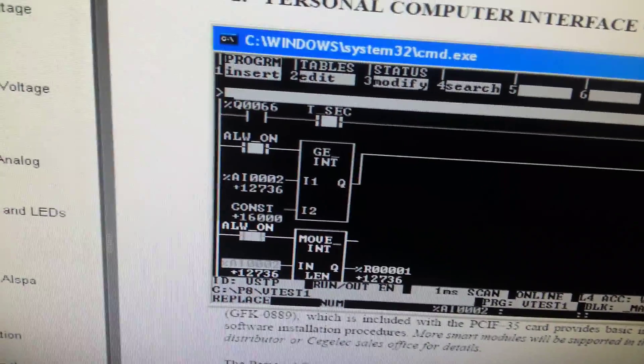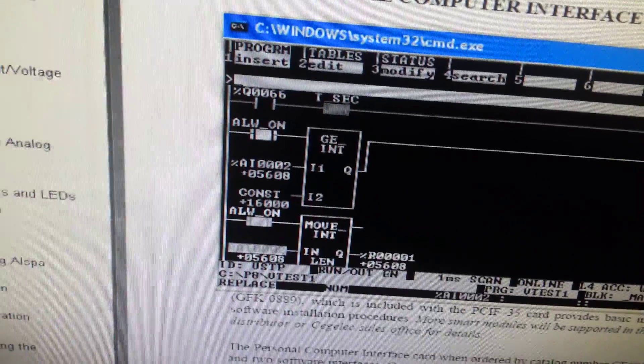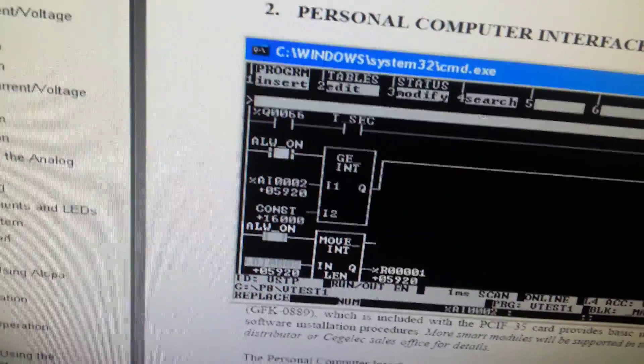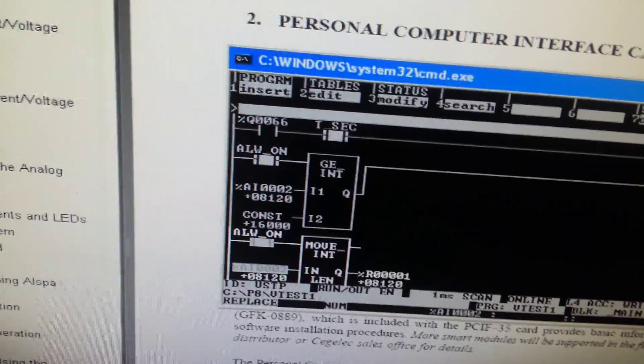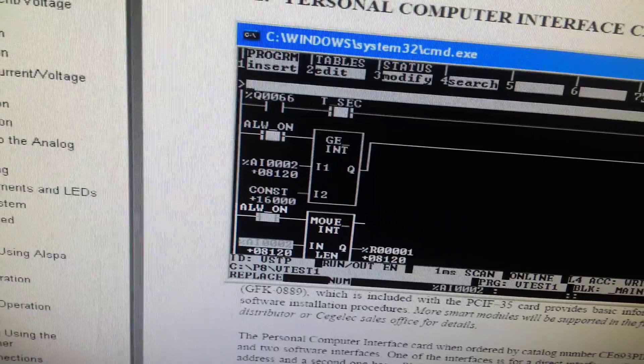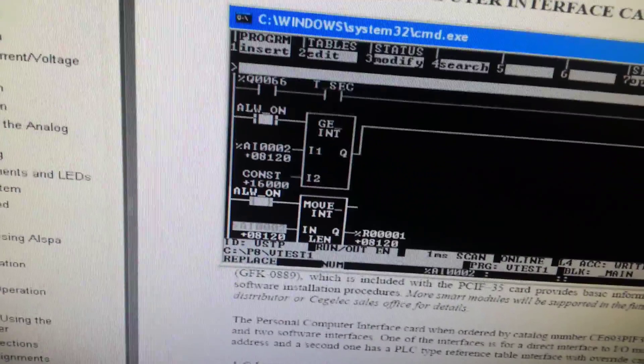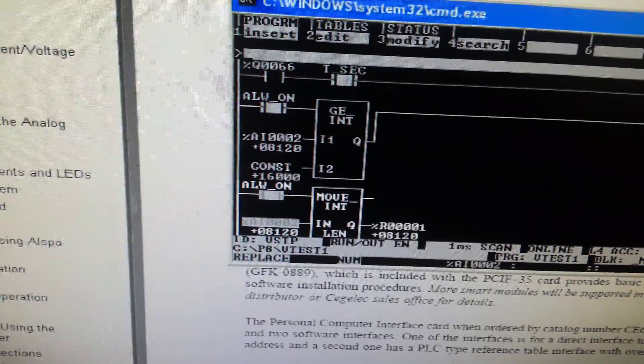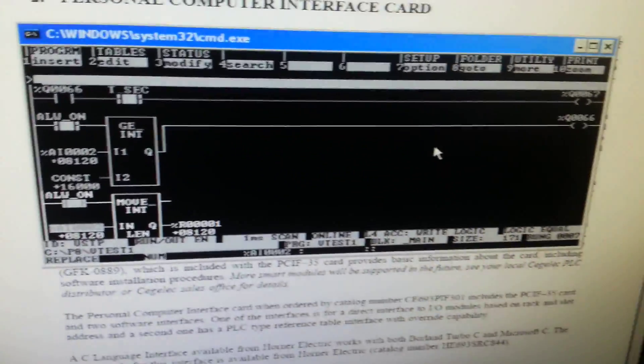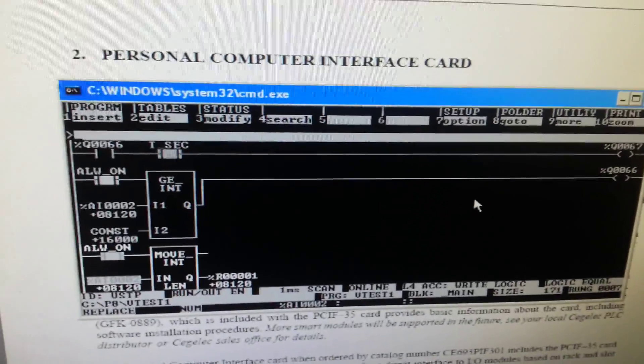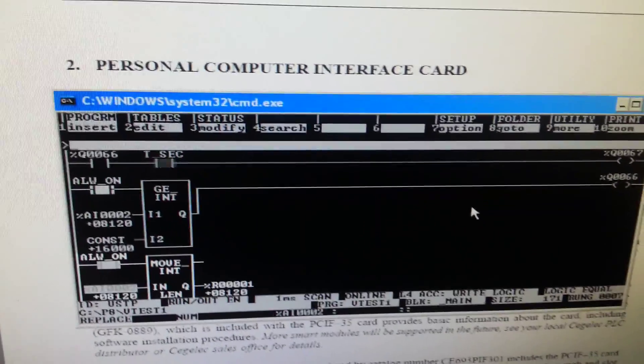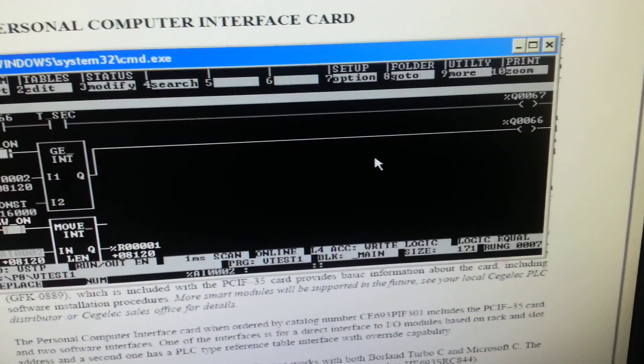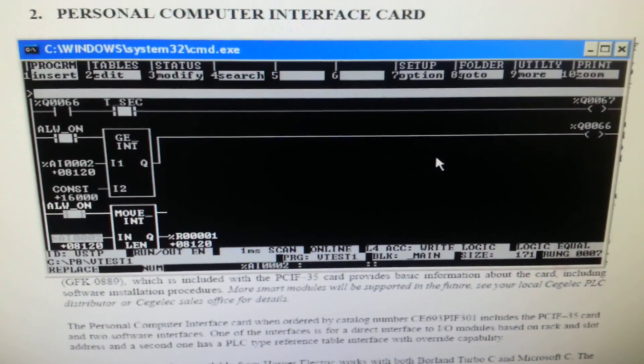When I come down to 8 milliamps, that is around 8,000 on the scale. Since 8,000 is less than 16,000, Q 0066 gets de-energized, and Q 0067 is also de-energized.